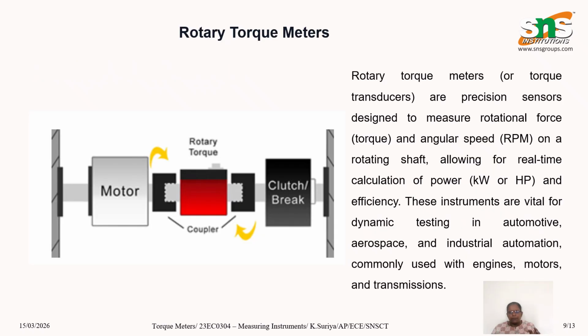So one important type of torque meter is the rotary torque meter. So they are designed to measure torque in rotating shafts. They can measure both rotational force and shaft speed simultaneously. Using these measurements, parameters such as power output and efficiency can also be calculated. Rotary torque meters provide continuous real-time monitoring while the shaft is rotating, making them highly useful in dynamic applications.